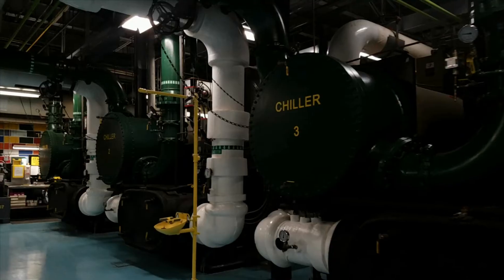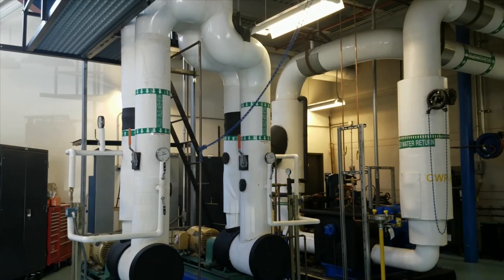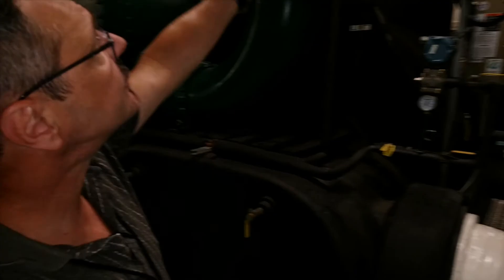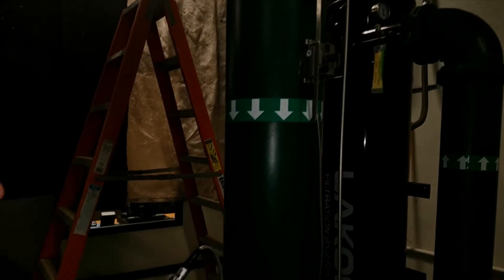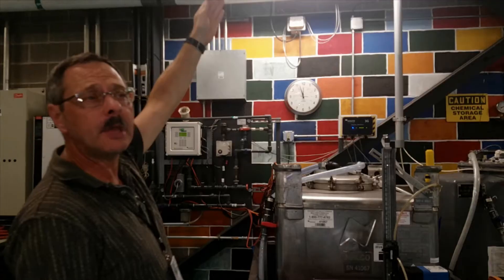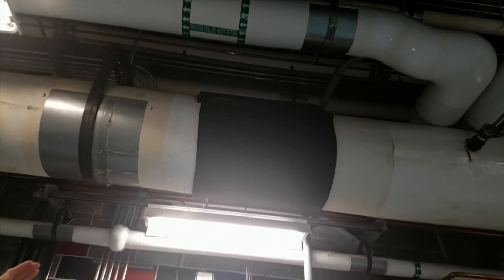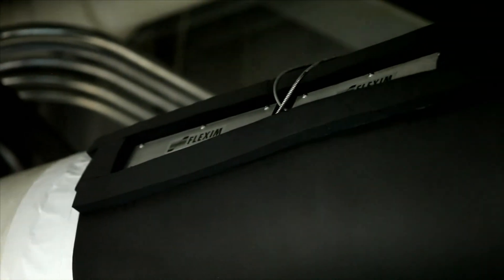In the wintertime when we have demand less than 600 gallons a minute, we need to make up that minimum load by bypassing some water. The equipment installed at the time couldn't turn down enough to actually regulate the control system as designed. Flexim came in and put a portable meter on, and we were able to measure flows far less than we could with the existing equipment. We then changed the control strategy from the old Vortex flow meter to the ultrasonic meter.